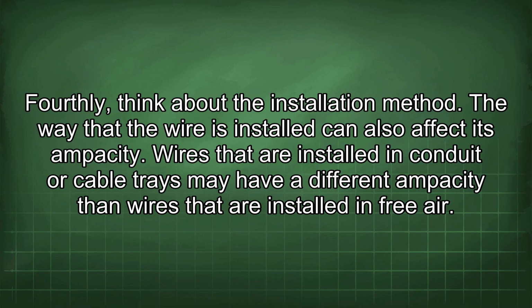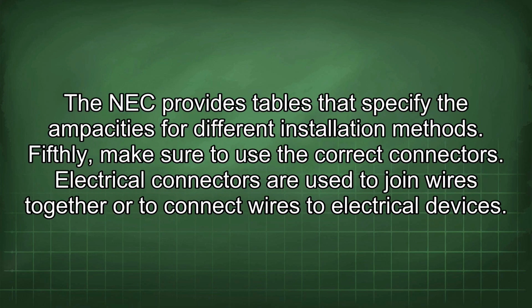Fourthly, think about the installation method. The way that the wire is installed can also affect its ampacity. Wires that are installed in conduit or cable trays may have a different ampacity than wires that are installed in free air. The NEC provides tables that specify the ampacities for different installation methods.